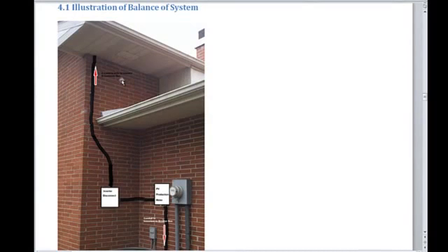Notice that it's very difficult to read where the conduit meets up into there, and where some of these connections are. So here's what we're absolutely looking for in this illustration. We've got to include the utility meter, which is right here. We've got to include the main service panel, service entrance, which is also right here. The main service panel is right there. The proposed layout of the balance of system, so that would be right here. The PV production scale meter, the inverter disconnect, and then maybe where the balance of system is.